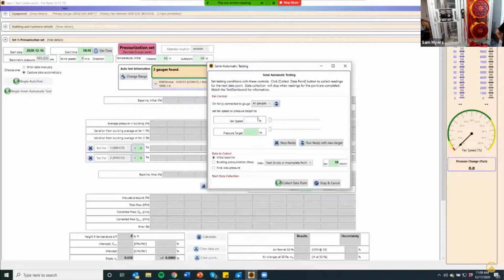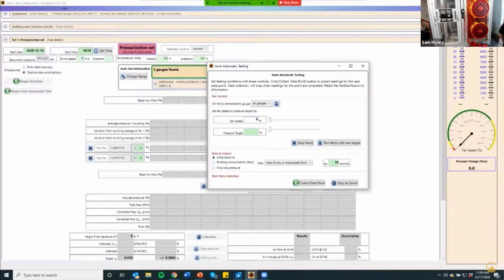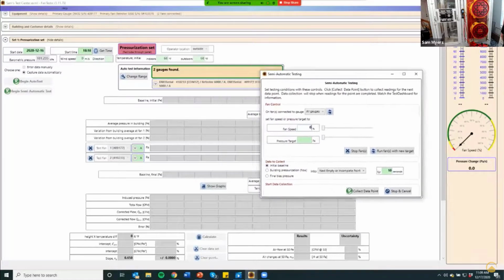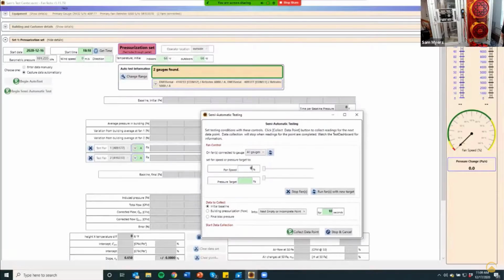For fan speed, it's going to want me to enter 0, because it needs to communicate with the fan somehow. It's going to take the baseline for 10 seconds, but I can change that if I want. If it's a super windy day outside, I might want to change that to maybe 20 or 30. The thing is, I can take as many baseline readings as I want, and it'll record them up here. So if I want to take 12 baselines, I can.